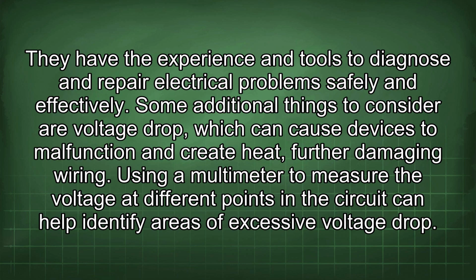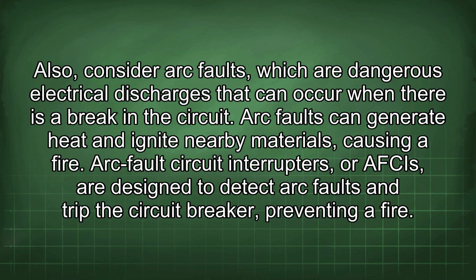Some additional things to consider are voltage drop, which can cause devices to malfunction and create heat, further damaging wiring. Using a multimeter to measure the voltage at different points in the circuit can help identify areas of excessive voltage drop. Also, consider arc faults, which are dangerous electrical discharges that can occur when there is a break in the circuit. Arc faults can generate heat and ignite nearby materials, causing a fire.